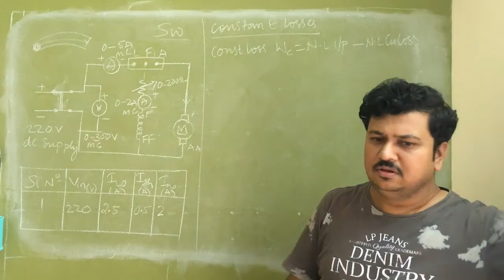I haven't connected any load to this motor. Therefore, output provided to the load by the motor is 0. Whatever the power it is receiving from the source is completely consumed by the motor itself, and the power consumed by the motor is a loss for me. So whatever input power I am getting at no load is completely loss power. You should remember this, whether it is a transformer, DC motor, or induction motor. If there is no output connected and the machine is drawing some power, that entire power drawn at no load is a loss, because load is not there, output is not there.